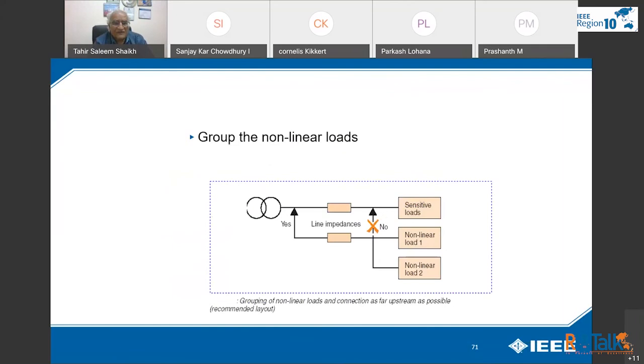Then group the non-linear loads. That is, you will have a separate bus bar for non-linear loads and a separate bus bar for sensitive loads. This is a general phenomenon. You will have a separate source.